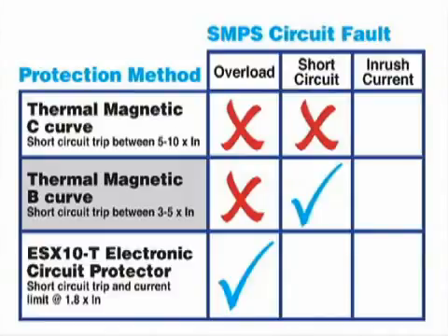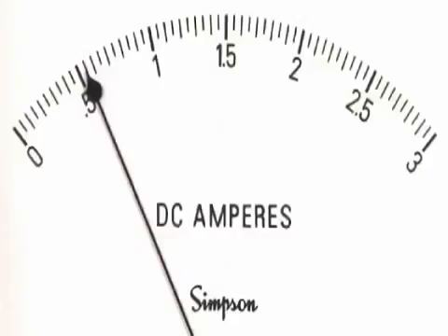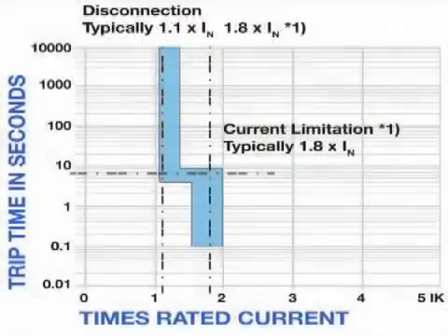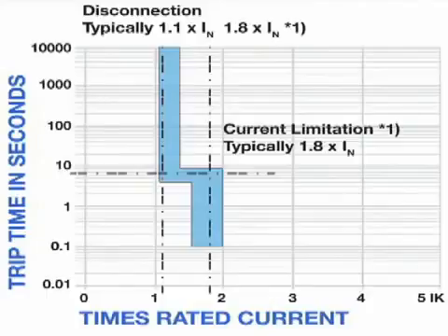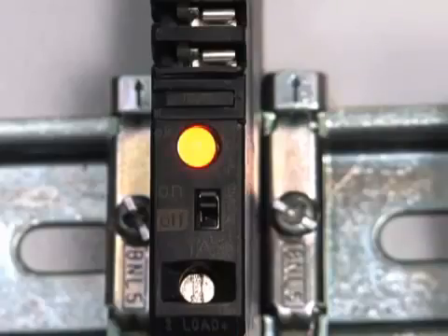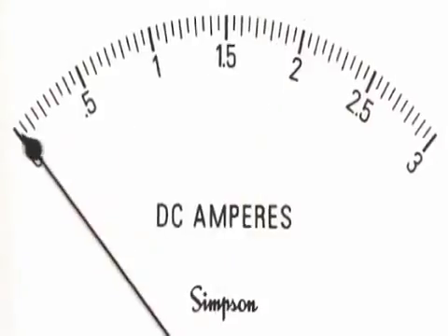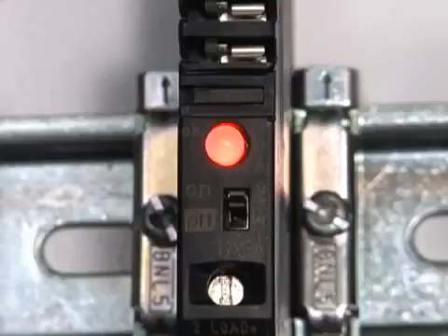Now, let's simulate a short circuit condition on the ESX10T. As you can see, for short circuits, the current is limited to 1.8 times the rating of the protector and is electronically disconnected immediately. If the short circuit is present for 3 to 5 seconds, the breaker must be reset as indicated by the red LED.